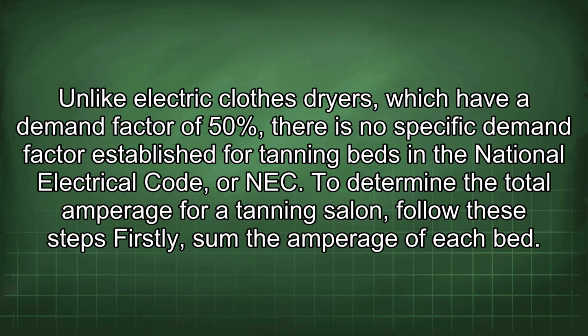Unlike electric clothes dryers, which have a demand factor of 50%, there is no specific demand factor established for tanning beds in the National Electrical Code, or NEC. To determine the total amperage for a tanning salon, follow these steps.